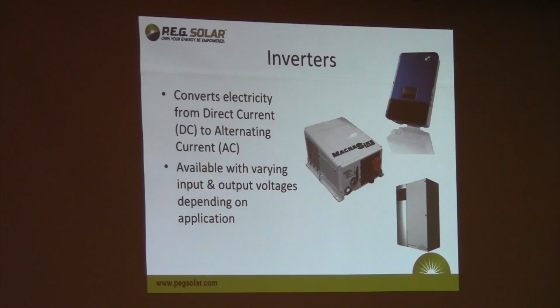So it's not uncommon for a system we do for home backup to wire the solar panels at an operating voltage of about 100 volts per string, running into an MPPT, a maximum power point tracking controller, which will step that voltage down to either 14 volts for a 12-volt battery charge, 28 volts for a 24-volt battery charge, or about 55, 56 volts for a 48-volt battery bank. Most battery banks for home backup are at 48 volts DC now.